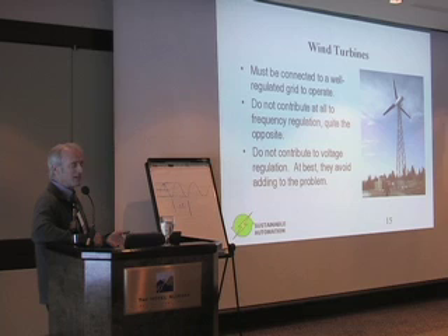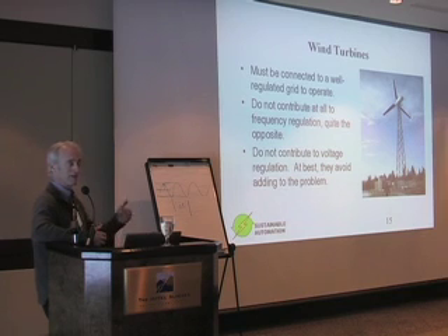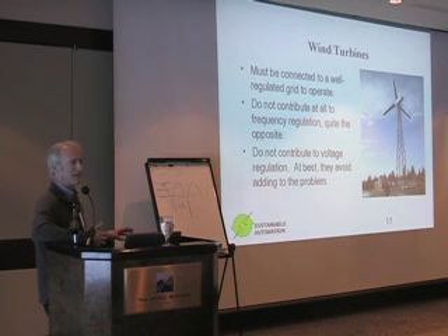There's a caveat that I should mention here. Some, especially more modern wind turbines with full power conversion in the generator itself, in other words, a power electronic converter that's the interface between the machine and the grid, have the ability to control their reactive power load. Generally speaking, especially in the smaller size range, at best they avoid contributing to the voltage control problem by not introducing additional reactive power load. They don't actively participate in controlling voltage. That's left to the other devices in the system.